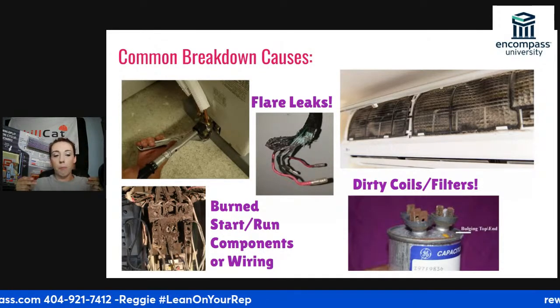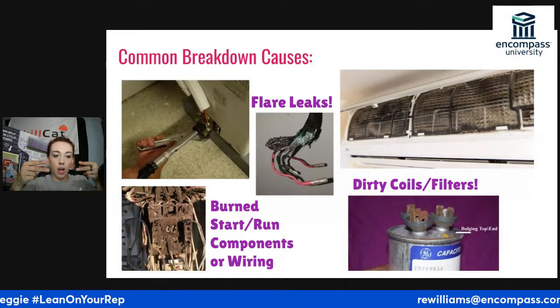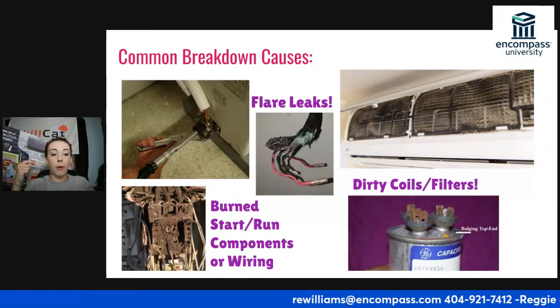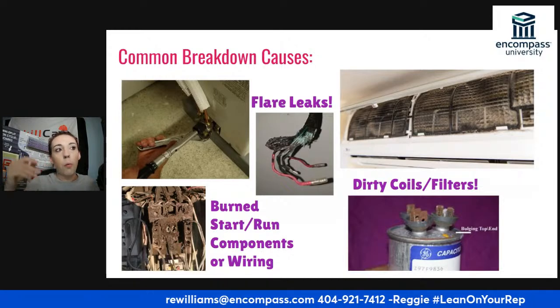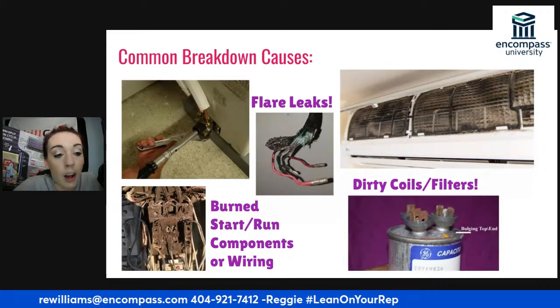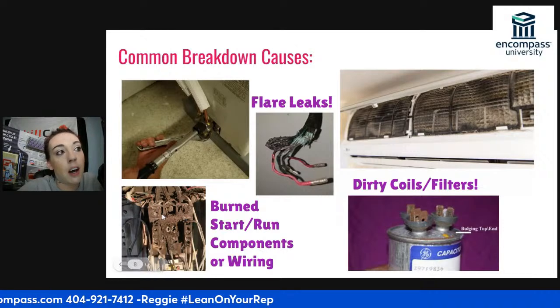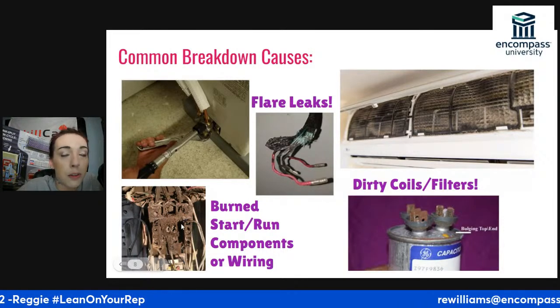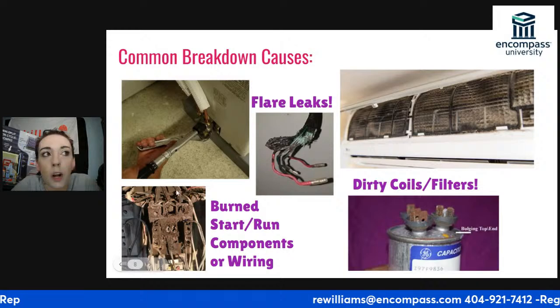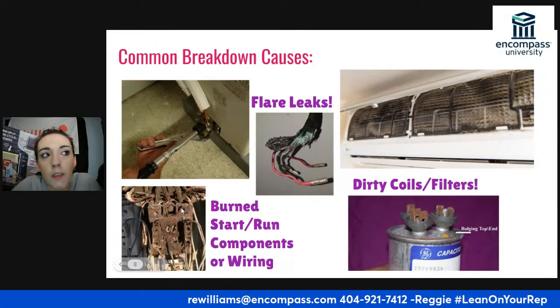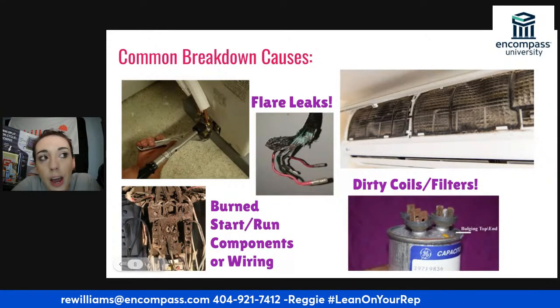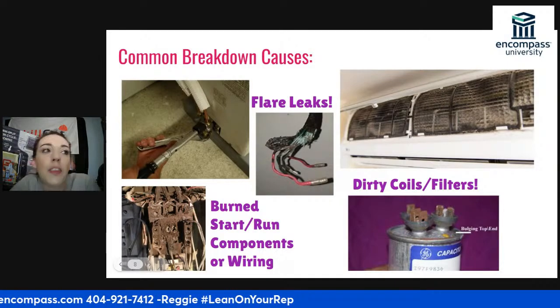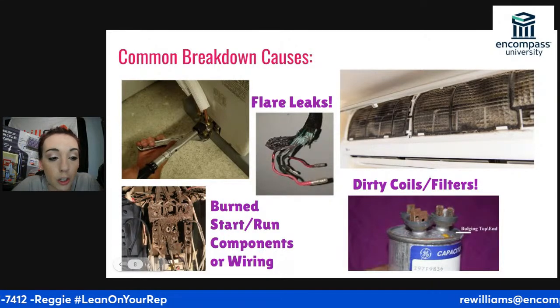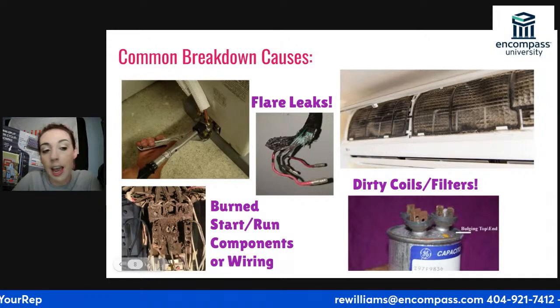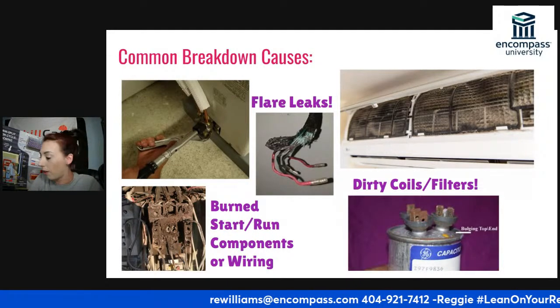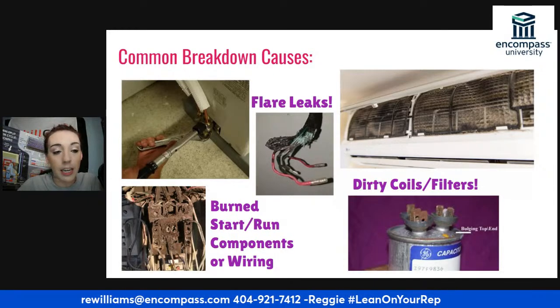So when you have a contactor pulled in and it's not able to make a good connection, those contacts will do this. They will jiggle, and then we'll end up with a kind of sound. When it runs like that for a long time, we end up with charring on those contacts. So you won't typically see anything on this face here. Sometimes the burn will be bad enough that it will burn the wire up here or one of the outsides of the plastic casing. But usually you have to look behind here at these little contacts and see if they are charred or cooked. Those can be cleaned with a wire brush. They have a product called contact cleaner that you can spray on, and you can kind of do it that way.